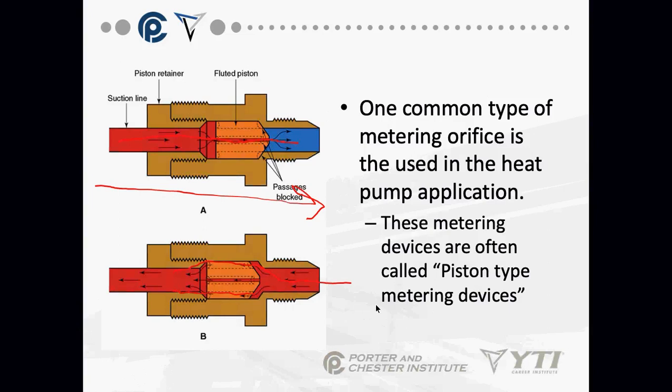So what makes this not efficient? Because it still can't tell, it is either all or nothing in each direction. Okay, it's not metering. Can't change the quantity of refrigerant. Okay, so this little orifice in the center here, where I just drew my arrow, doesn't get larger or smaller based on the load on the system. Okay, it's still a fixed orifice.